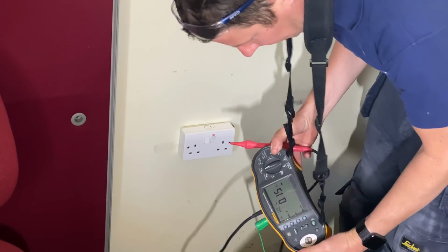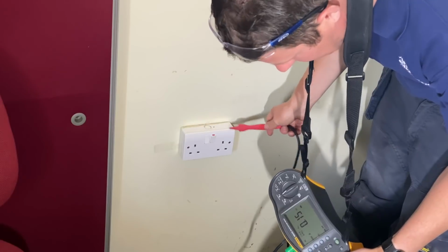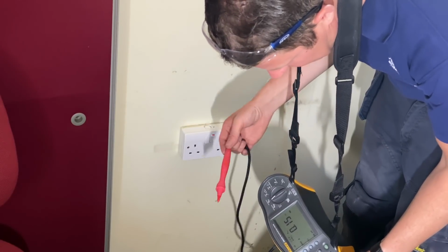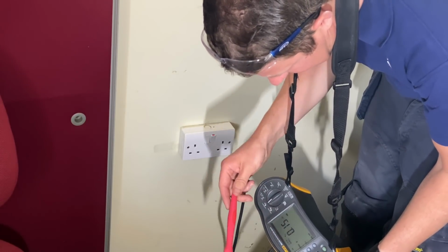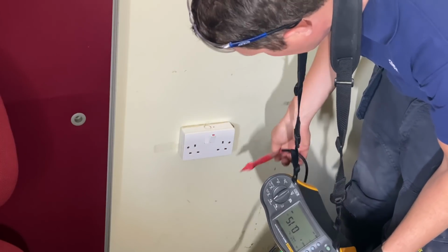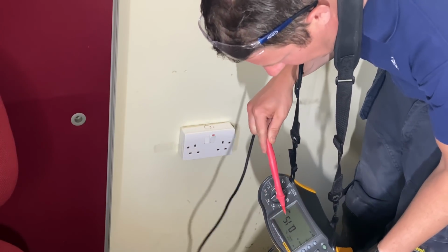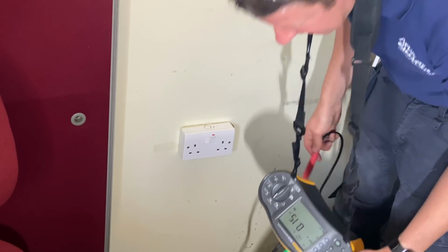So this is an example of a typical test. So that socket outlet, which is quite close to the consumer unit, the resistance of R2, which is the resistance of the circuit protective conductor from the consumer unit to this point, is 0.15 ohms, which is perfectly acceptable.